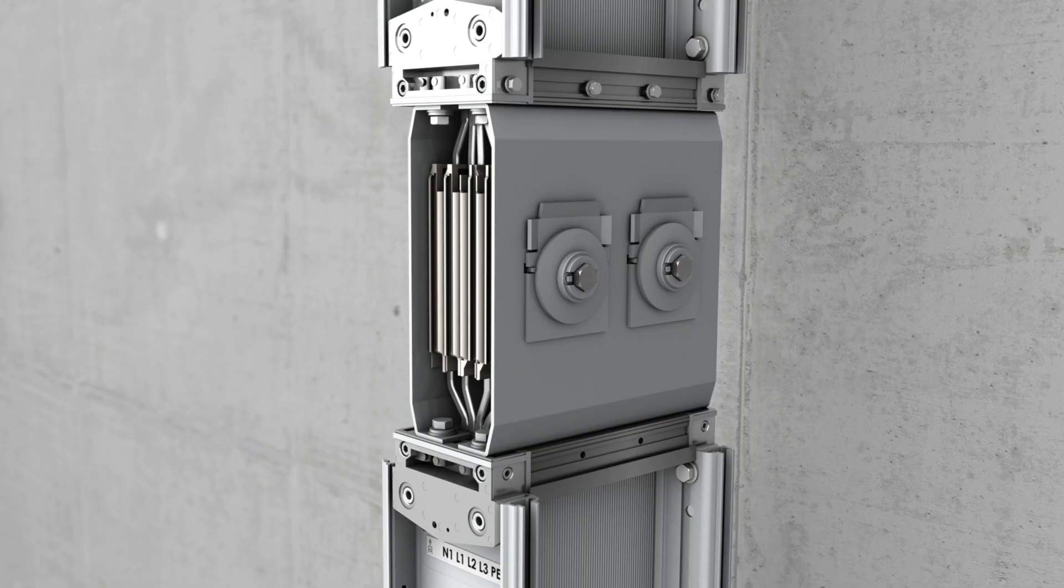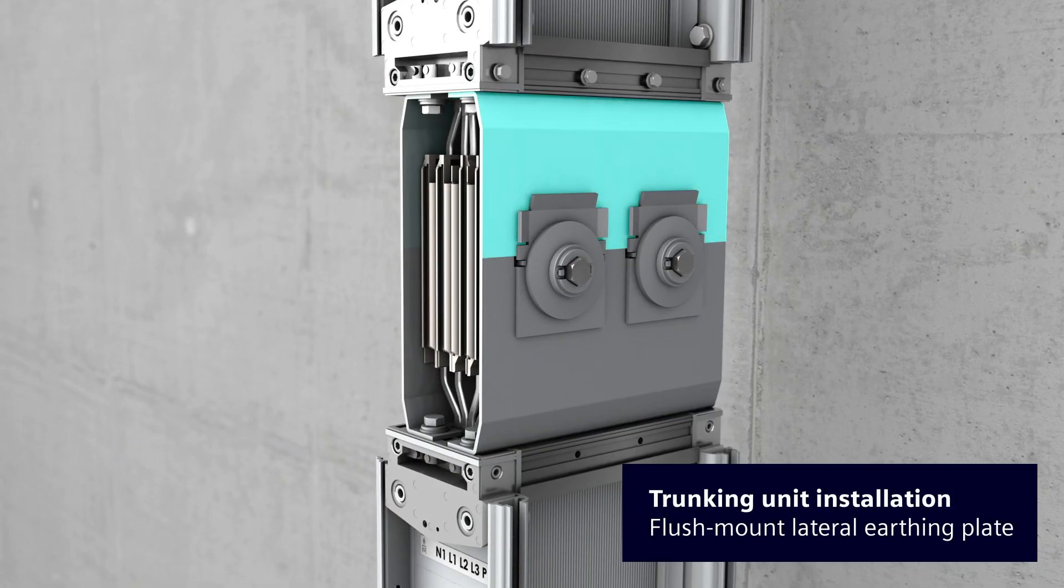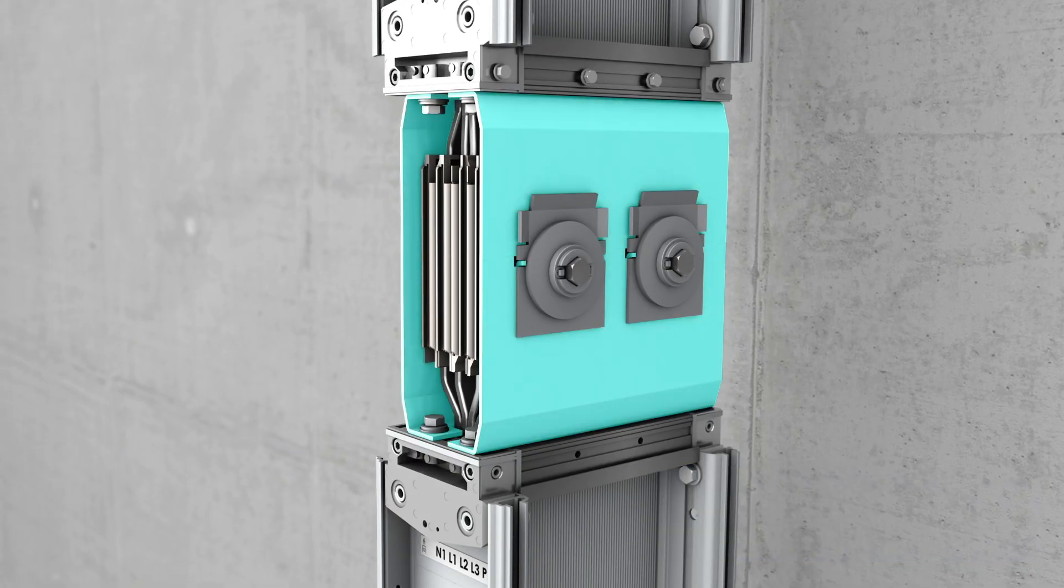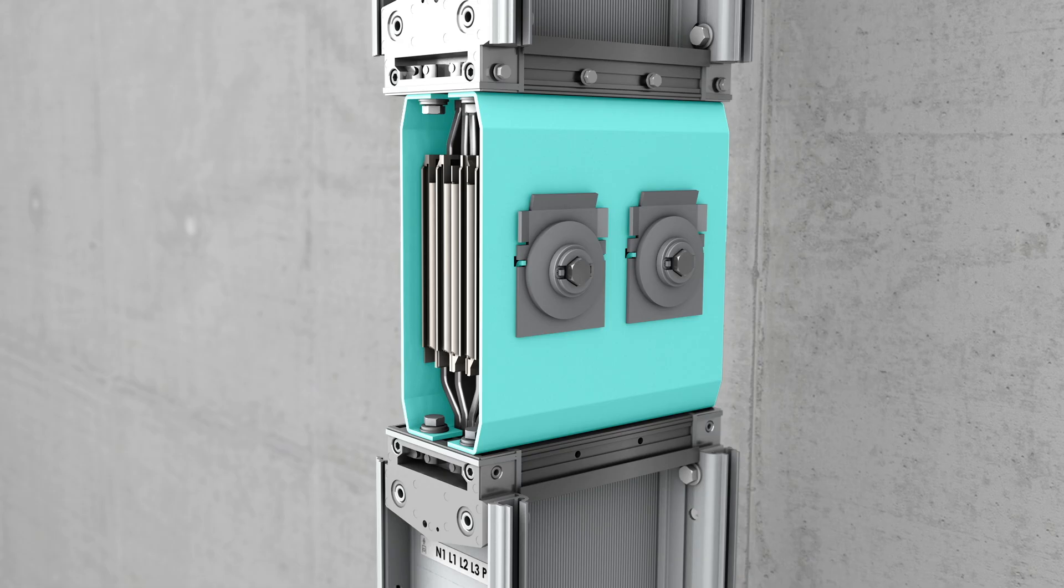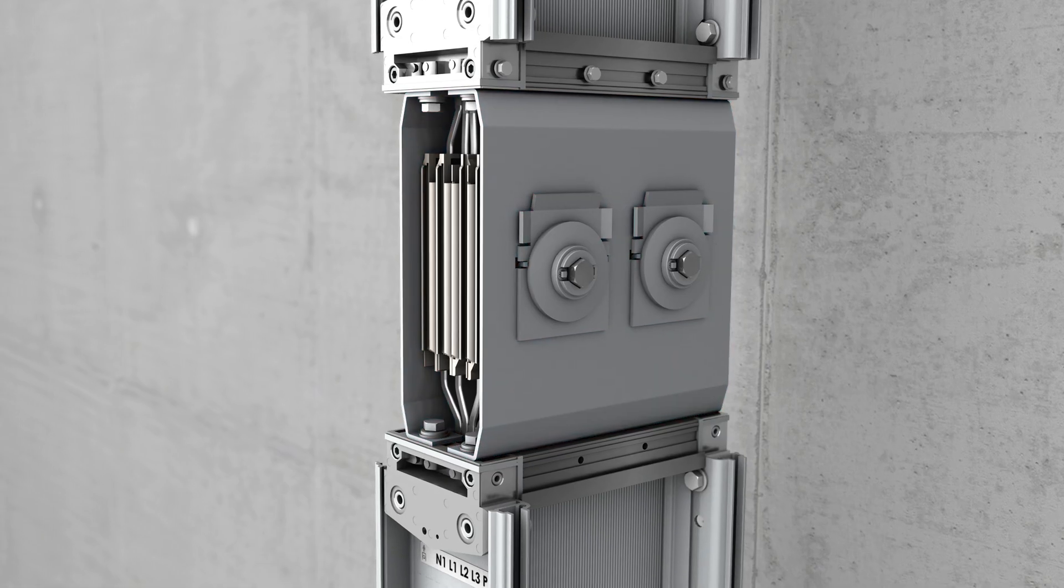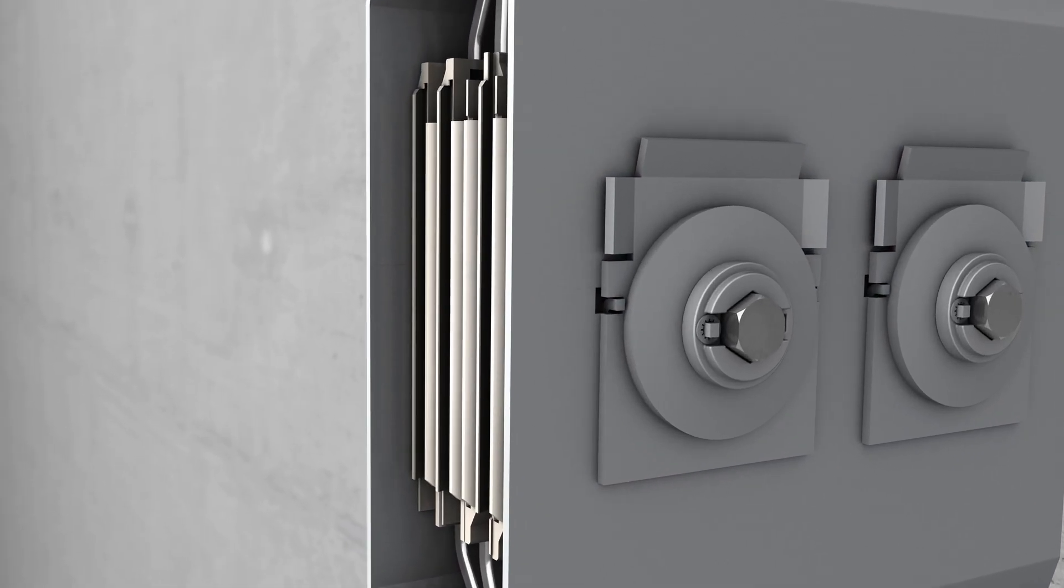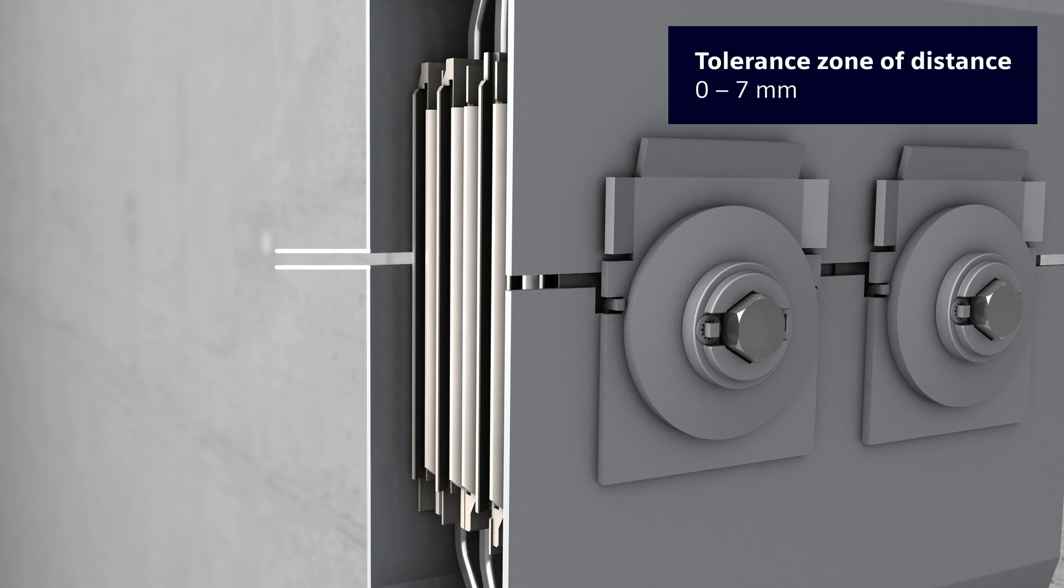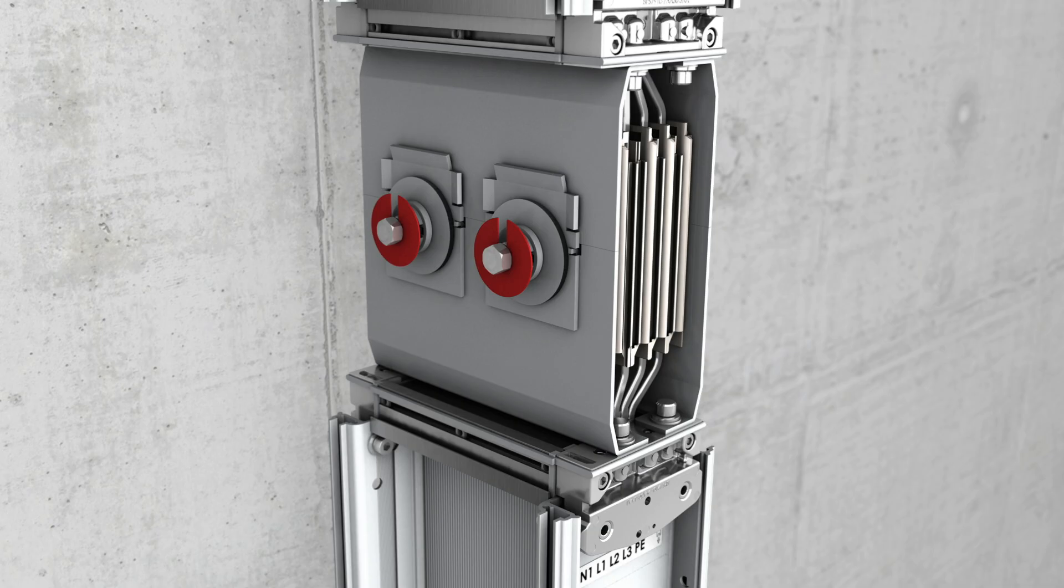Make sure to position the lateral earthing side plates flush against the two trunking units. Check the distance between the two trunking units. The distance between the trunking units at the earth side guide plates must be within a tolerance of 0 to maximum 7 mm. The terminal block is then positioned correctly.